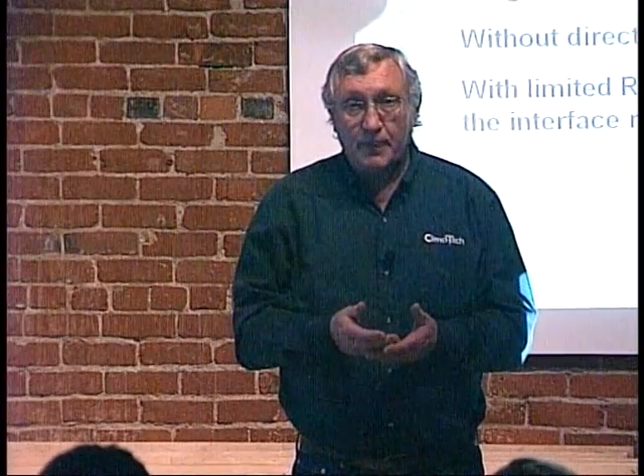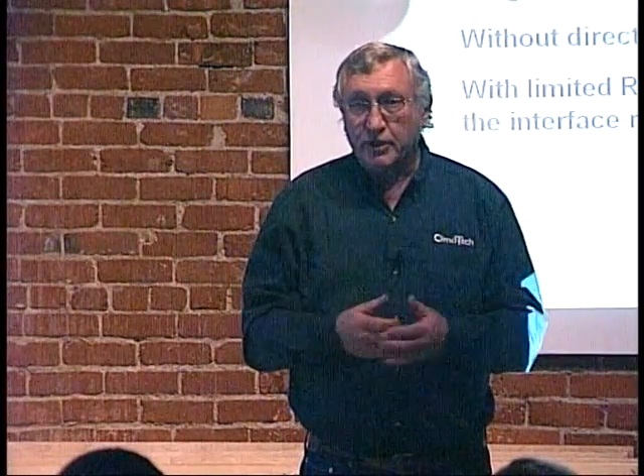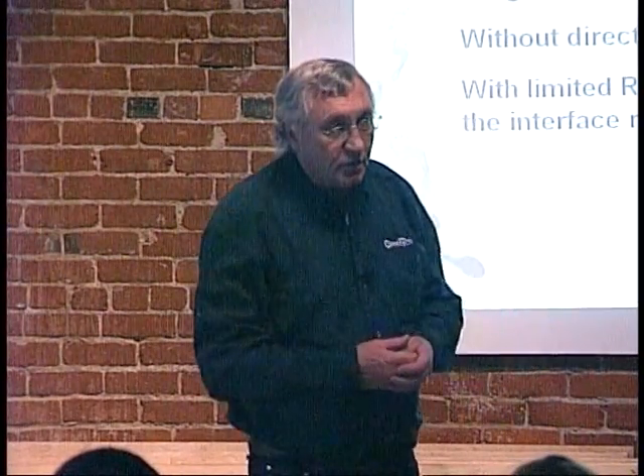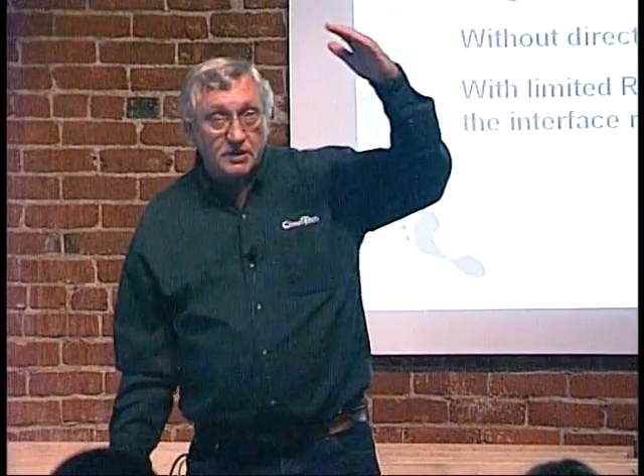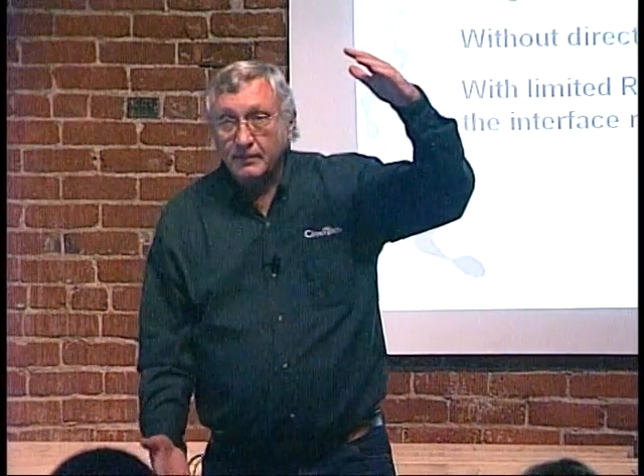And that's all we had. That doesn't work bad, right up until you want to go to an unoccupied mode. When you go to an unoccupied mode, you might want to change the cooling set point to 85 and the heating set point to 60. And you only got a 5 degree dead band. It's really tough to get there.